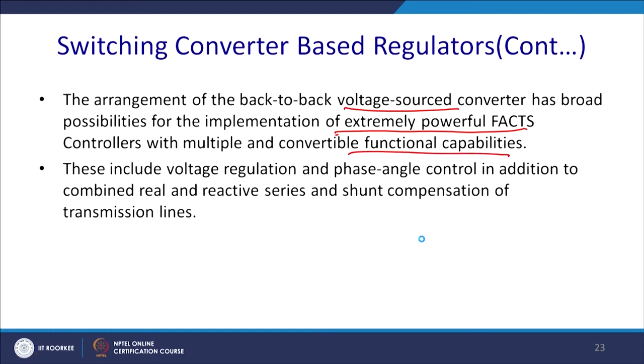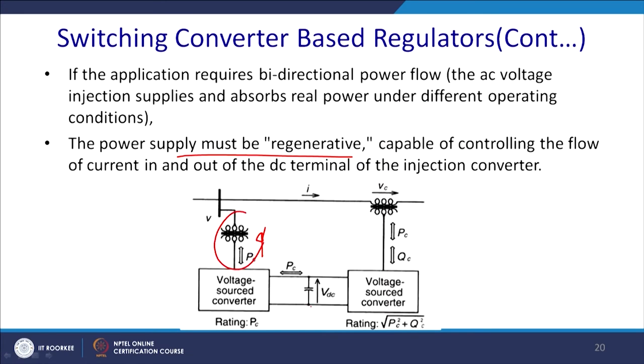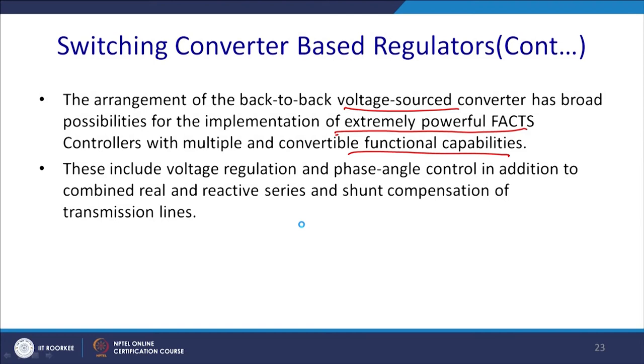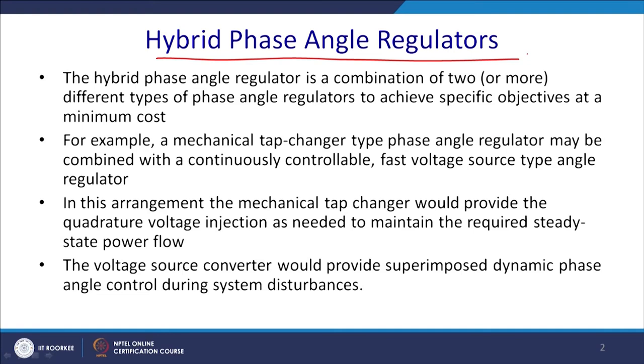And what happened here is that this converter essentially holds the DC-link voltage, and thus the other converter on the right-hand side can work very well. This includes voltage regulation and phase angle control, in addition to combined real and reactive power and series compensation of the transmission line. So, this phase angle regulator is called a hybrid phase angle regulator. We have seen that in most cases the voltage is injected in quadrature to shift the phase. Then can we do something so that we can inject in any phase and optimal compensation can be achieved?